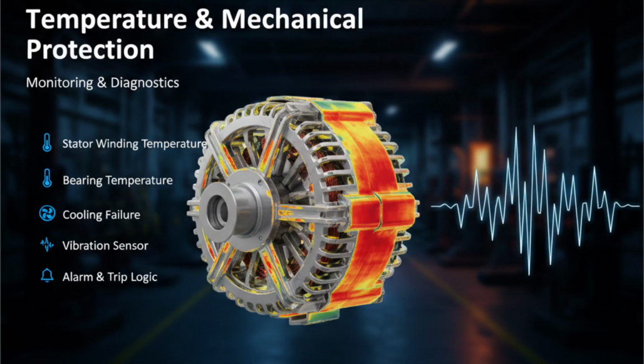Temperature or mechanical protection. Thermal protection is critical. RTDs embedded in stator windings monitor temperature continuously. Bearing temperature sensors detect lubrication problems. Cooling failure can cause rapid temperature rise. Vibration sensors detect rotor imbalance or misalignment. Usually, protection systems provide alarm first. If temperature continues rising, automatic trip occurs. Preventive maintenance reduces such failures significantly.